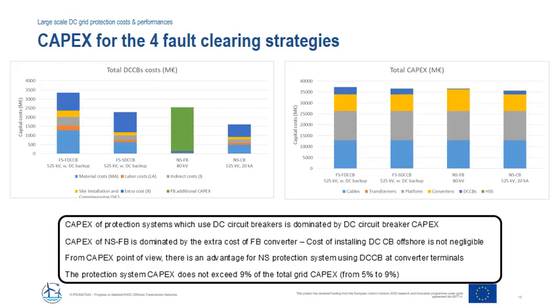The capex of the full bridge-based strategy is dominated by the extra cost of the converter, which seems to make it less competitive from a cost perspective. Additionally, the costs associated with the DC circuit breaker's weight and volume, here depicted in dark blue, especially if the DC circuit breakers are installed on an offshore platform, are not negligible. From a capex point of view, there is an advantage for non-selective protection systems using DC circuit breakers at converter terminals. Finally, it can be observed that the protection system capex does not exceed 9% of the total grid capex.